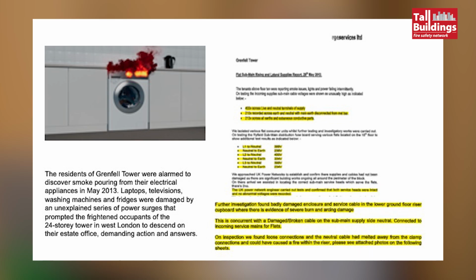Every single floor in a tower block will have a separate sub-supply. Guardian, if you install it on each of those sub-supplies, it would have alerted to that problem before it became dangerous. It would have told the management company, you need to come out, you need to resolve the problem, and Guardian will actually specifically tell them what the problem is, whether it's a loss in neutral, loss of earth, it will do any of them. So once it's installed, it's 24-hour monitoring, but with also the opportunity, if the management company fail to respond, it can shut the supply down on that individual floor, but none of the other floors in that building.